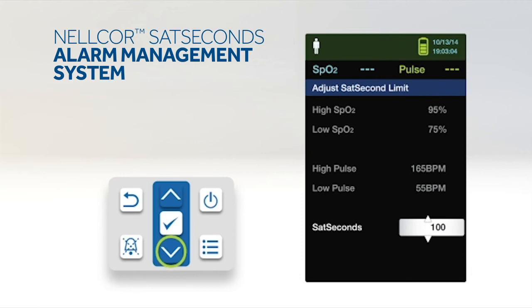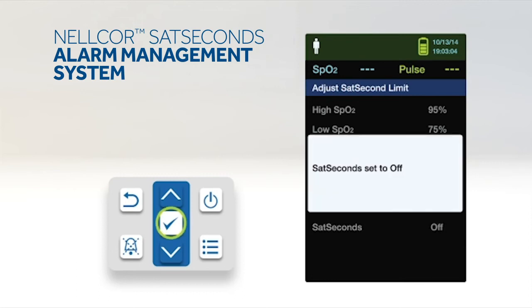Press the down arrow to change Nellcor SatSeconds to 50, 25, 10 or off. Note that the default value is 100. Finally, press OK to select the value.